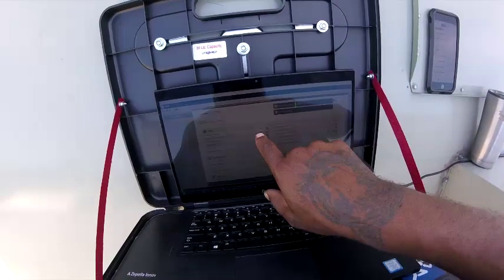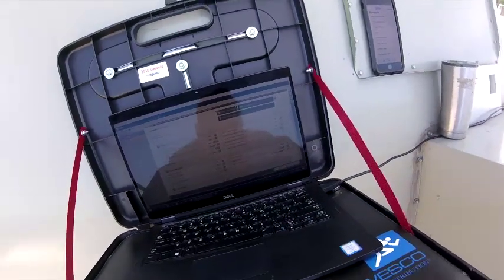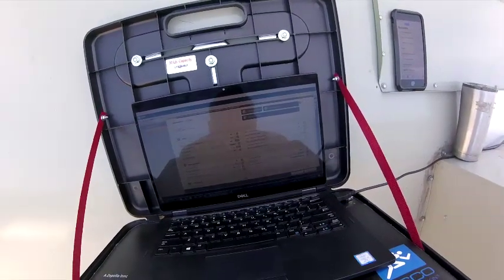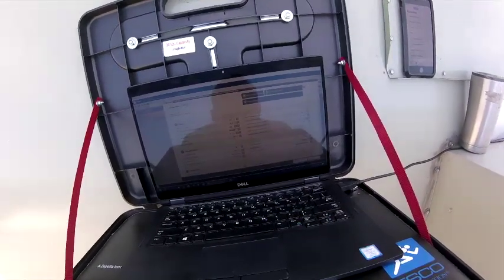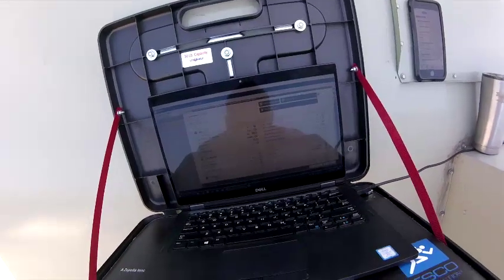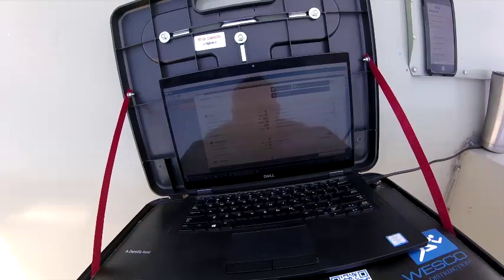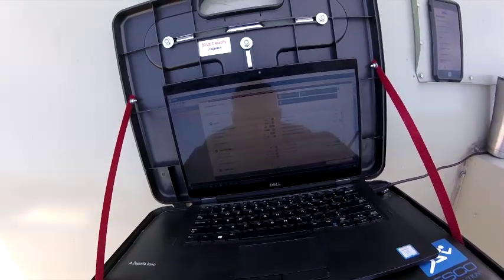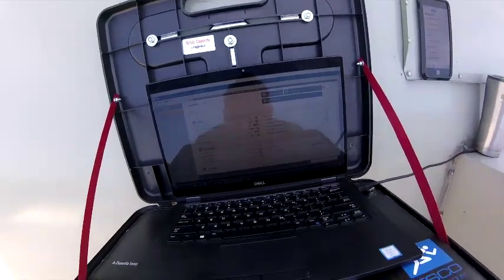Look at my discharge, 48 now. So he's going to call me back and kind of let me know. But he said it should be a lot better since he changed the min and the max on the fan power box. Like I said, it's been an ongoing issue, so this unit may be okay now since he changed that min and the max. Because as those fan power boxes open and close, it should also change my duct static pressure up here.